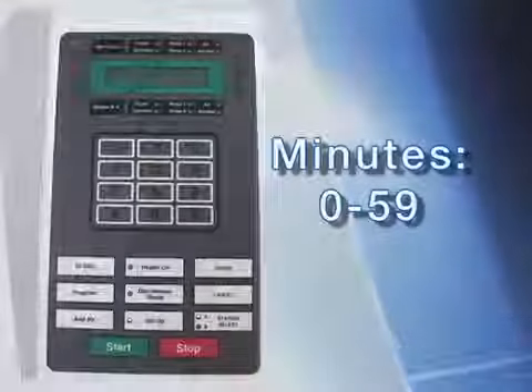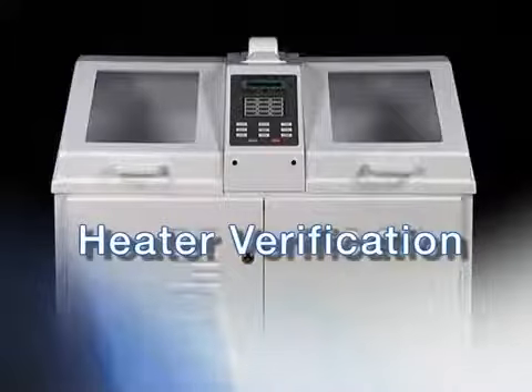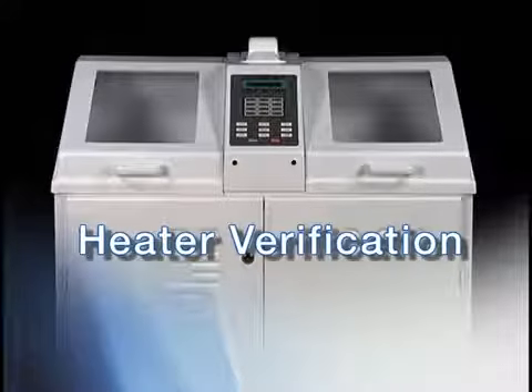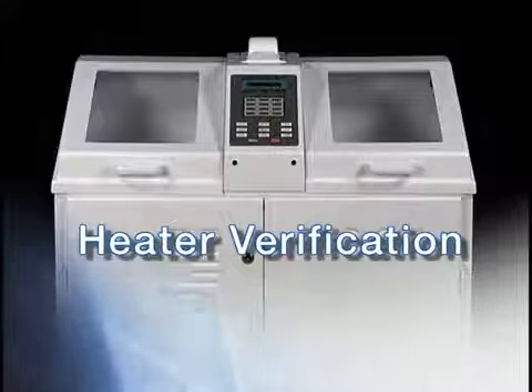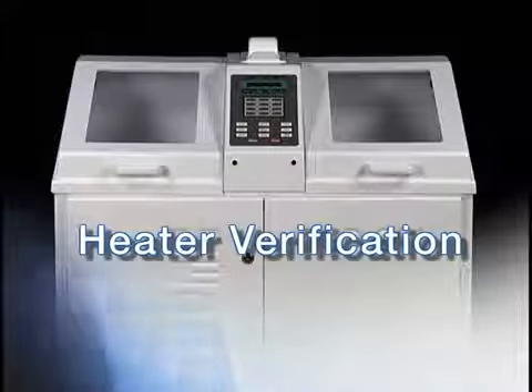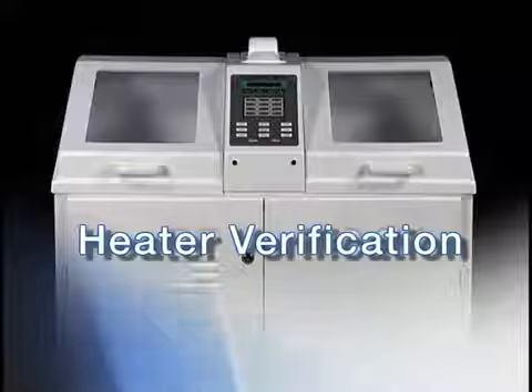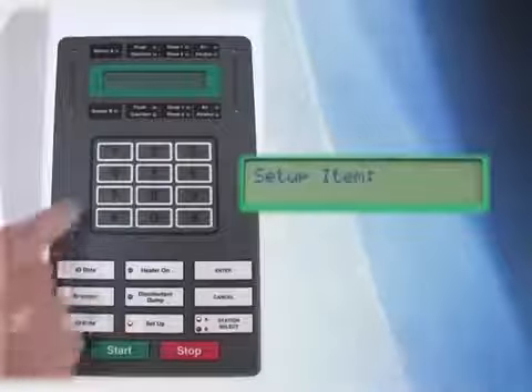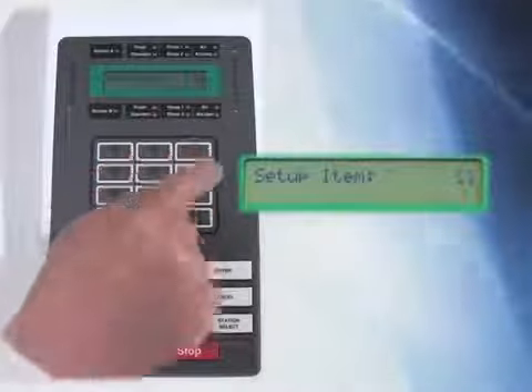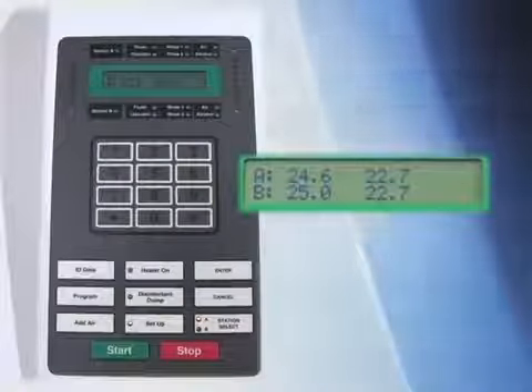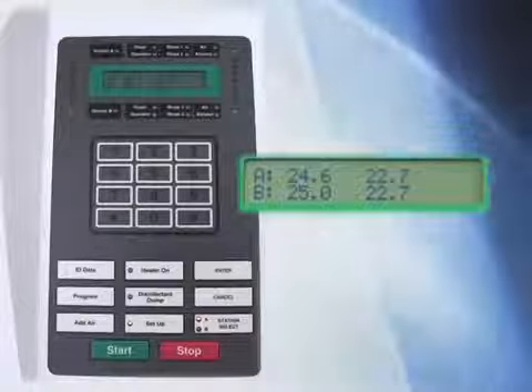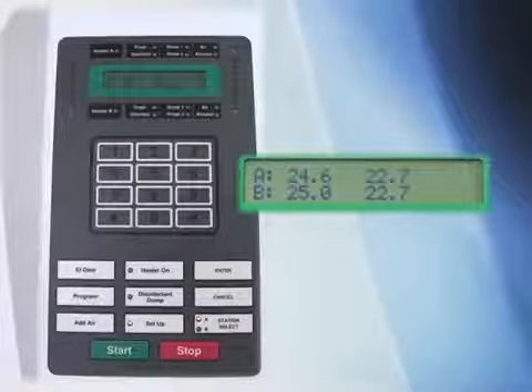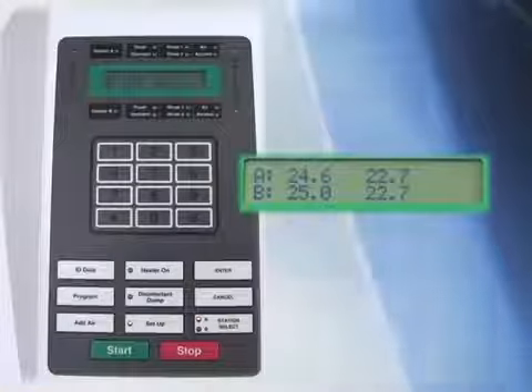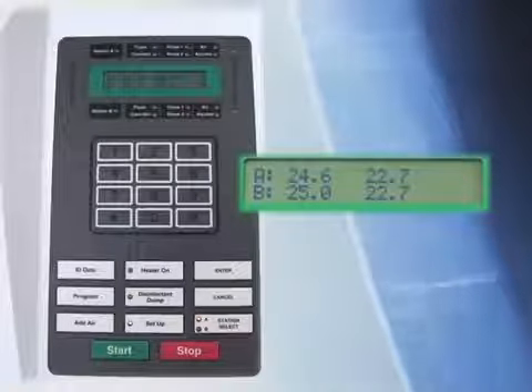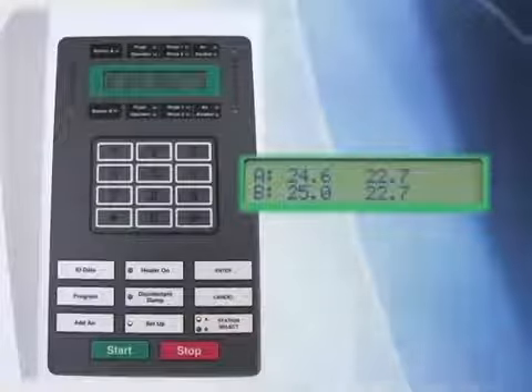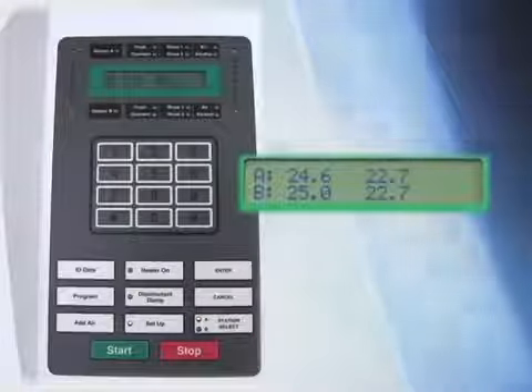Press Enter. One of the many useful functions of the DSD-201 is the ability to heat the disinfectant solution on a continuous basis. This enables you to begin reprocessing as soon as you are ready during the day. Press the Setup button. Press 1 and 3. Press Enter. Now you can see the disinfectant temperature. The left side of the display shows the basin temperature, the right side shows the reservoir temperature. Side A temperatures are shown on the top, and side B on the bottom of the display screen.